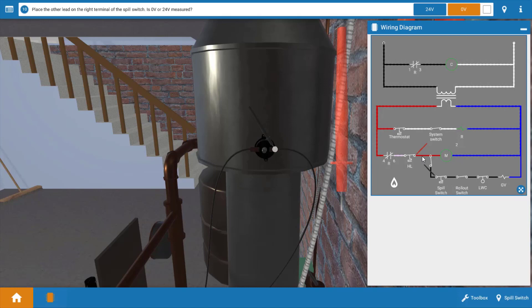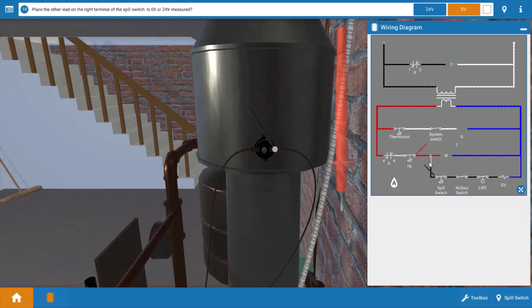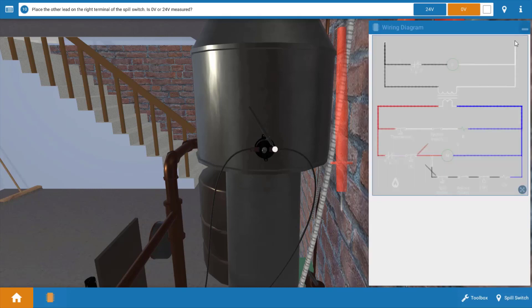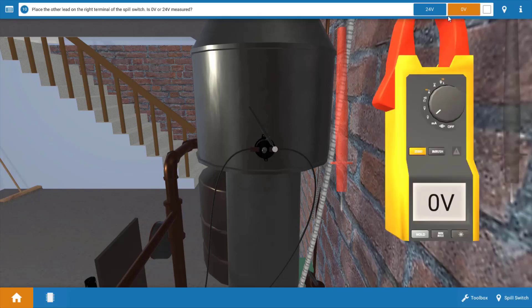When you look at your lead placement on the diagram, you're just simply reading right across this vent damper end switch. And because we read zero volts, that indicates no difference in potential and it verifies that the vent damper end switch has in fact closed. So we've got zero volts.